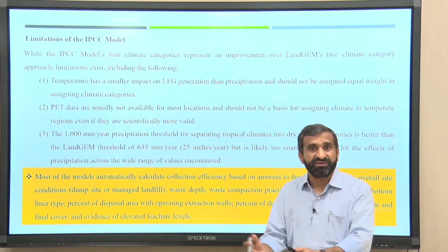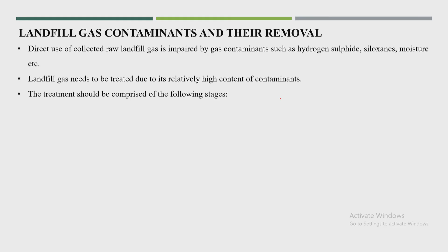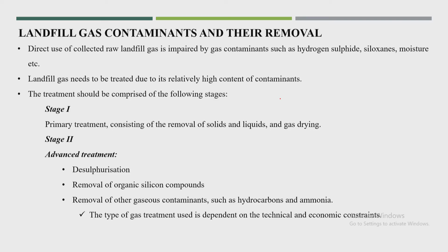Now, landfill gas contaminants and their removal. Direct use of collected landfill gas is impaired by gas contaminants such as hydrogen sulfide, siloxanes and moisture. Landfill gas needs to be treated due to its relatively high content of contaminants, and the treatment has stage 1 and stage 2. The primary treatment, which is the major one, considers removal of solids, liquid and gas drying, and stage 2 is desulfurization or removal of organic silicon compounds.